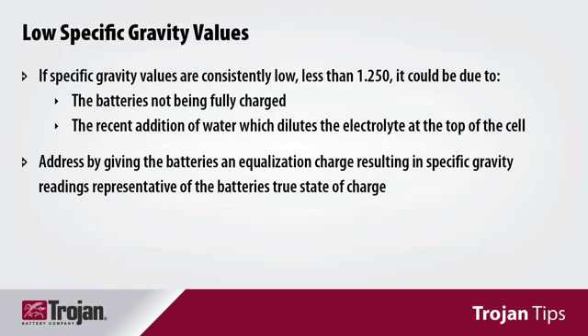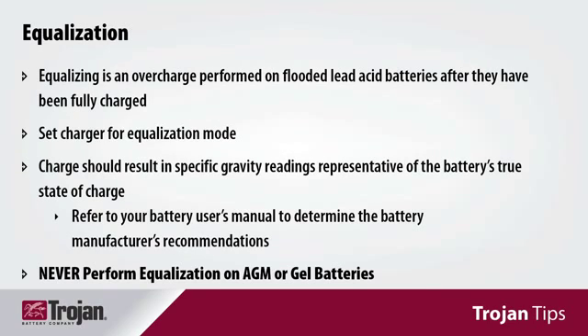If the specific gravity values are consistently low, which is less than 1.250, it could be due to the batteries not being fully charged or the recent addition of water, which dilutes the electrolyte at the top of the cell. In both of these conditions, the battery should be given a sufficient equalization charge that results in specific gravity readings that are representative of the battery's true state of charge.